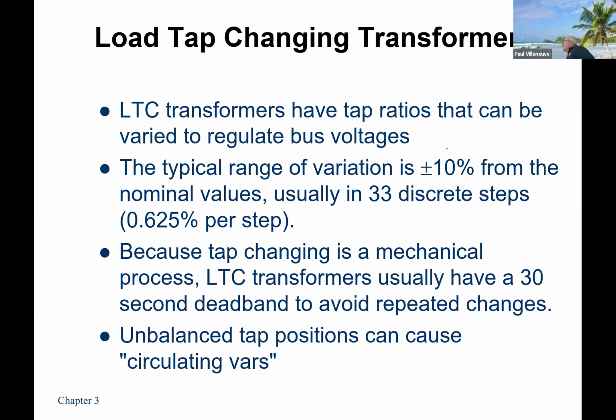Load tap changing transformers, very, very expensive, but you do find them. Load tap changing transformers are just what they sound like. If the voltage is too high or too low on your system, and it's been there for a while, you do a tap position change. Usually you wait at least 30 seconds for the voltage to be high or low, and then you make an adjustment. And it happens under load. You don't have to turn it off.